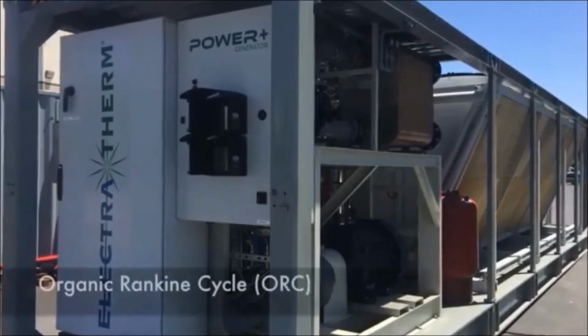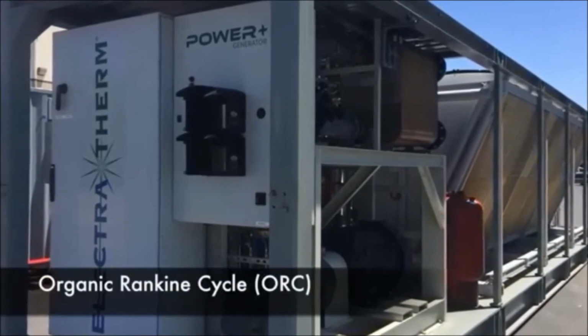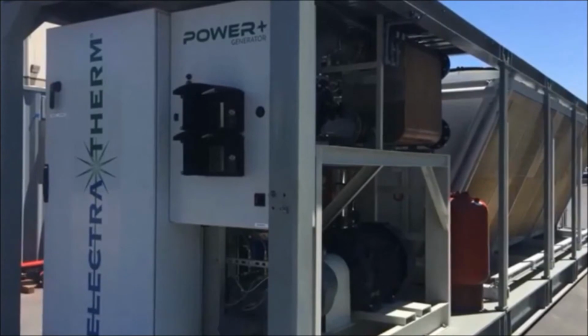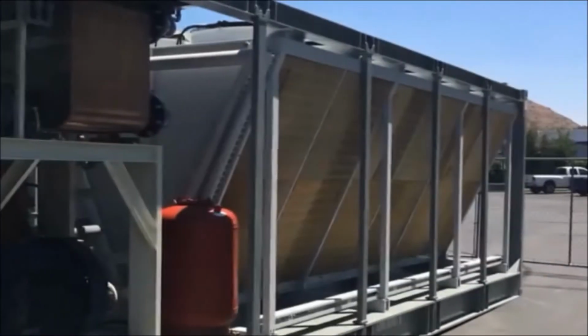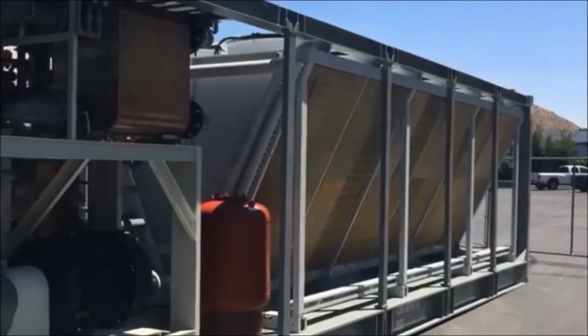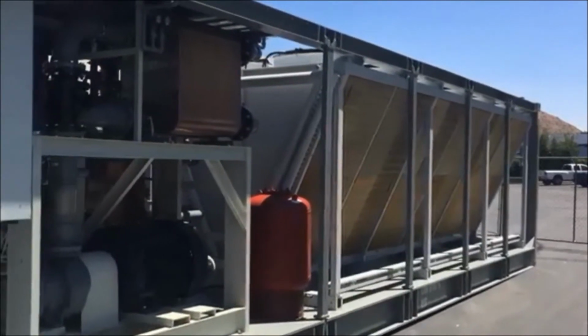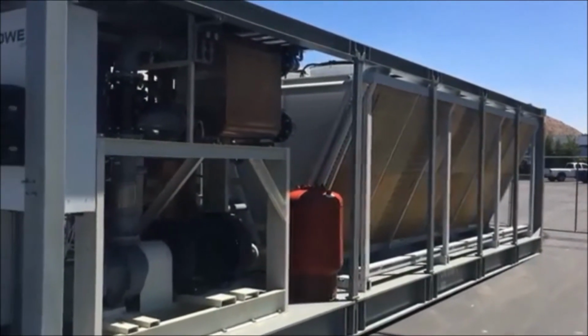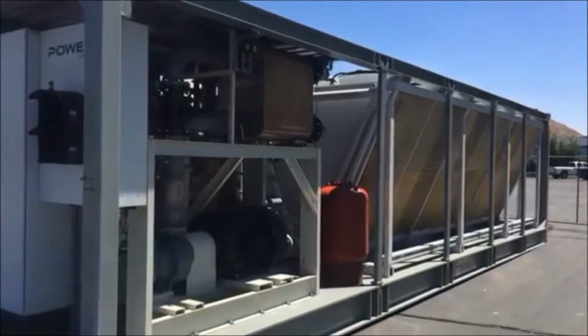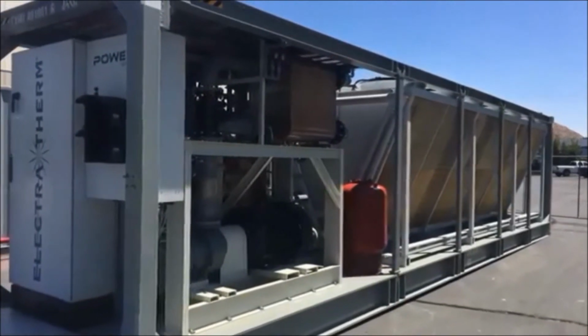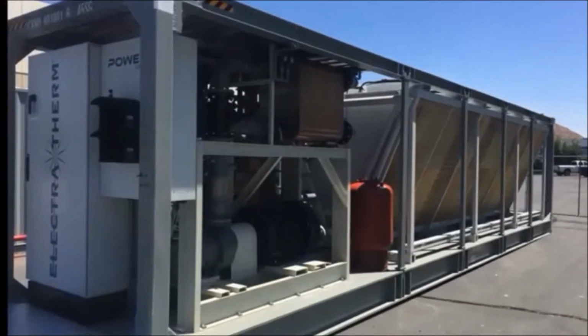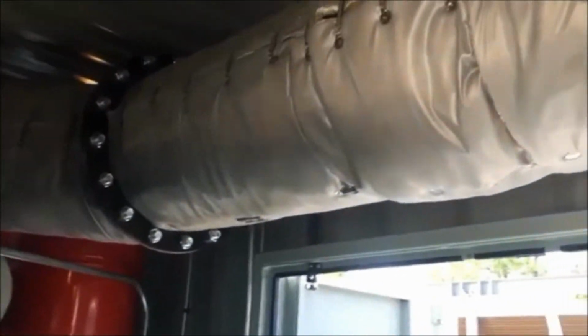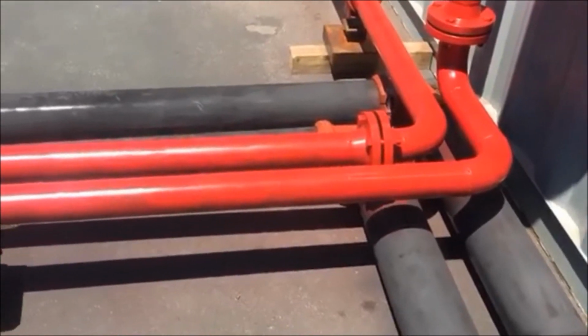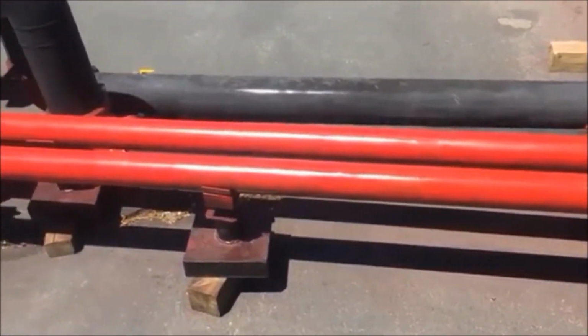The system uses organic Rankine cycle technology, also known as ORC, to generate the power. All engines need cooling, and so do ORCs. The ORC's cooling duty is larger than that of the engine, meaning the cooling required for the ORC is greater than what is required to cool the jacket water. Heat can be rejected from the engine's jacket water to the ORC condensing loop, ensuring a safe jacket water return temperature to the engine even when the ORC is turned off.